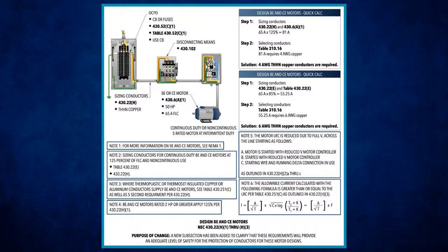Oh, I can tell you, because when they do the listing and labeling of that equipment, and they put that nameplate there with all the other information that's required on it by the NEC, they have to look at the NEC to make an assumption on something. So for them to put the minimum size breaker rating, they had to get a percentage from somewhere. Well, I guarantee you right now, Jeremy, I know 100% fact they got it from the National Electrical Code. And the ones that do follow that rule of you start at a minimum.